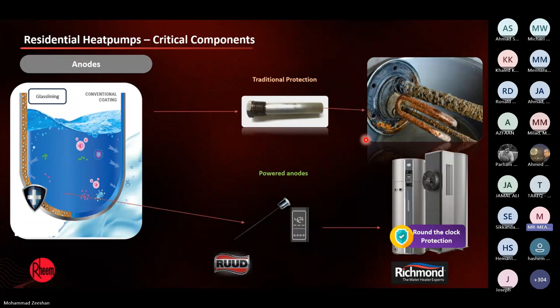So the powered anodes technically replace the magnesium anodes, so you don't have to replace it every 2 years. This provides 24/7 round the clock protection and ensures the tanks are protected all the time. So it's quite important to have powered anodes along with the magnesium anodes. Why along? Sometimes at your sites, when we supply the water heaters, there might not be any electricity since the commissioning of the project, so to protect during that time we will have a magnesium anode all the time. Also during power cuts, which we thankfully don't see much in GCC, the tanks are protected all the time. This is why it's important to have both anodes, magnesium and powered, built in to protect the tanks.